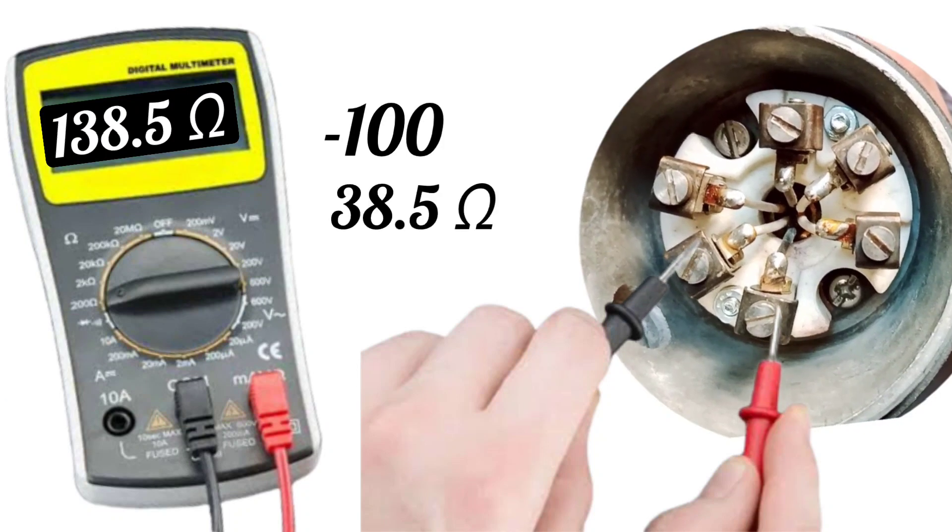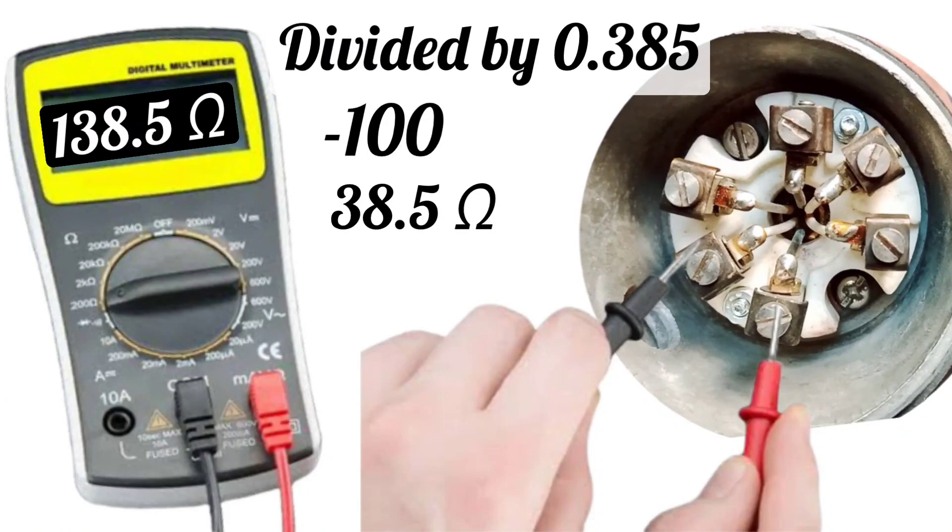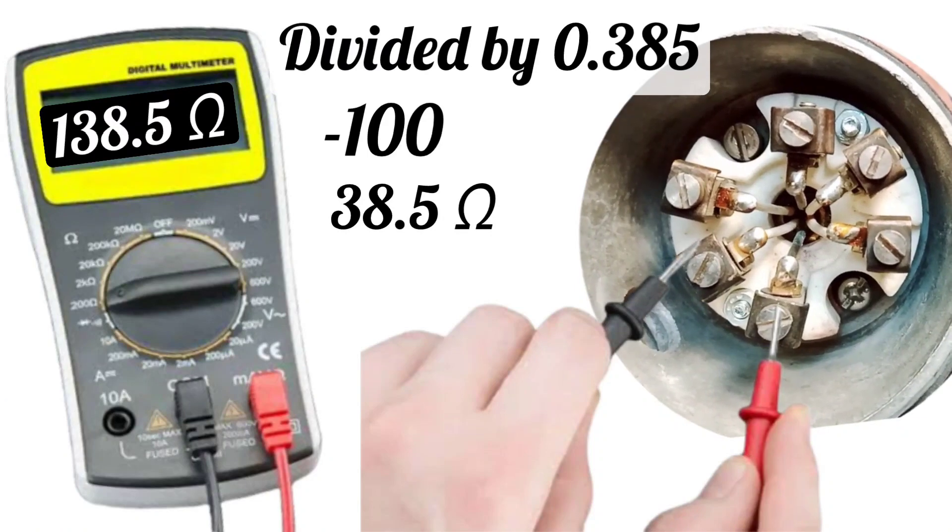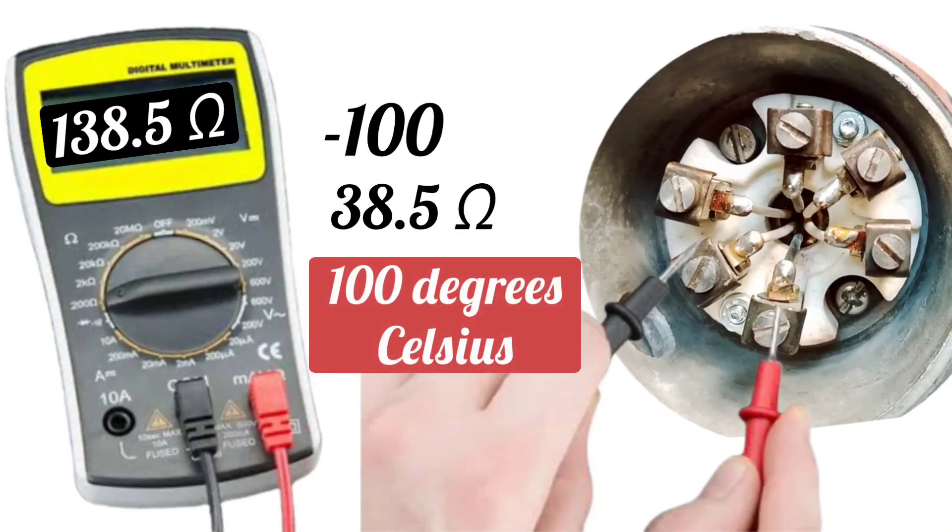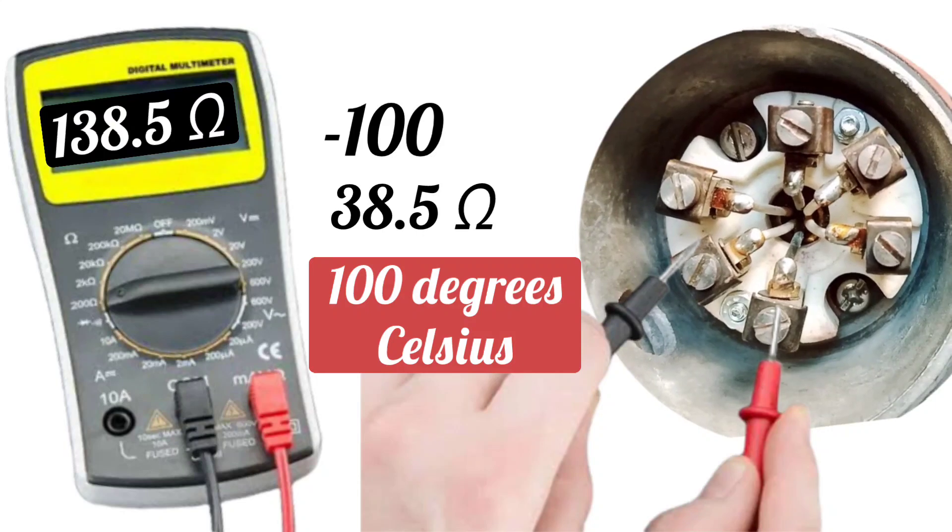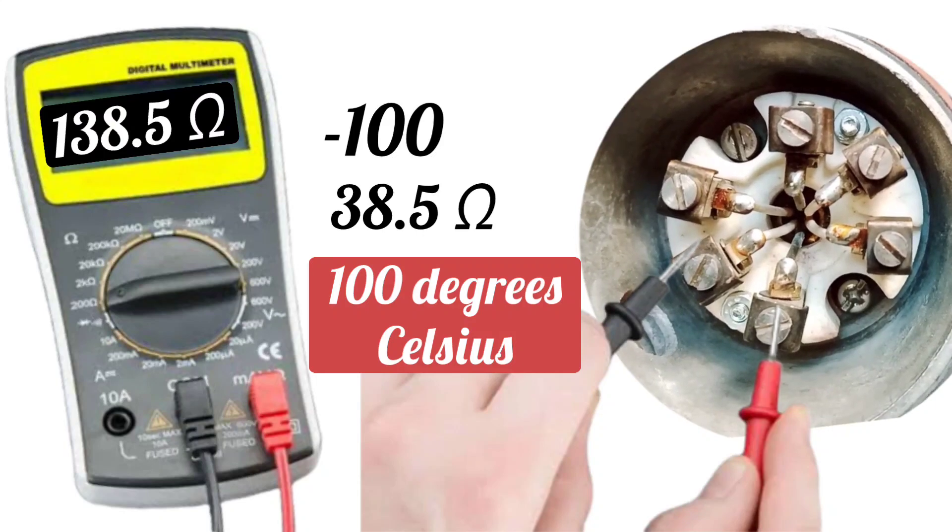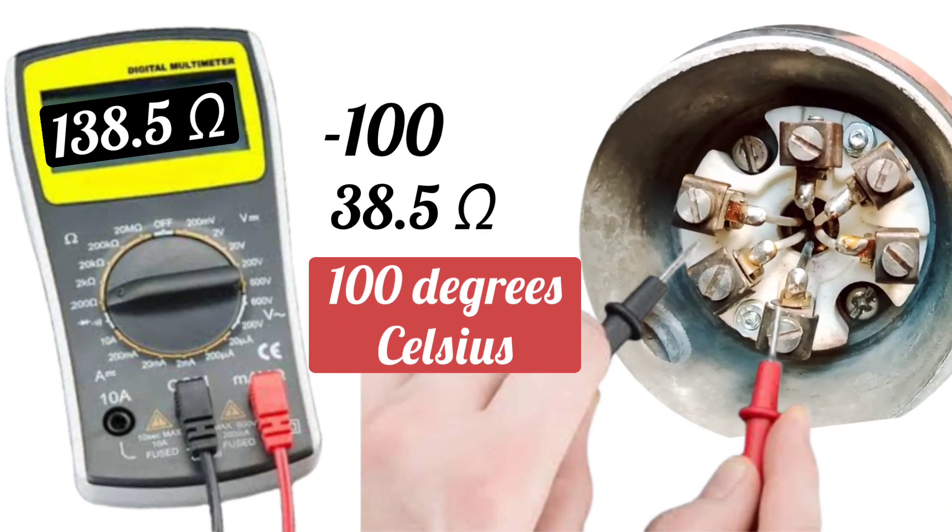When we divide it by 0.385, it will be 100, which means 100 degrees Celsius temperature will be on that place. If resistance is showing 138.5 ohms, let's solve it with other method.